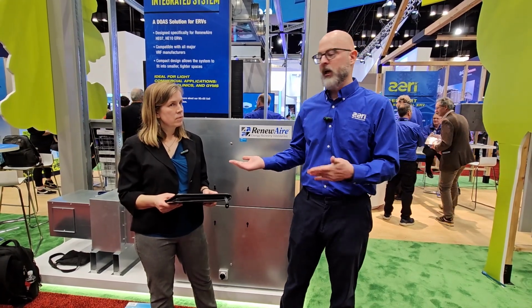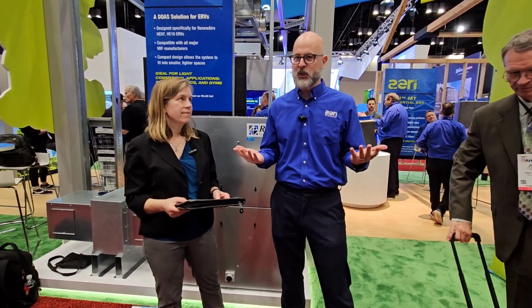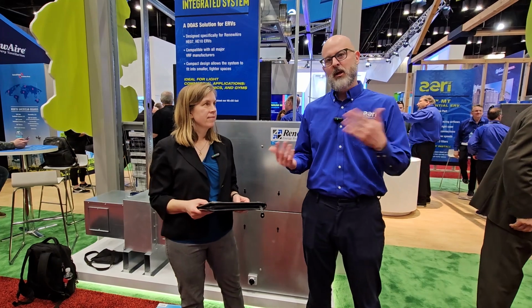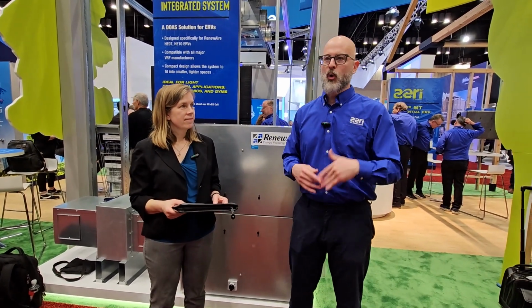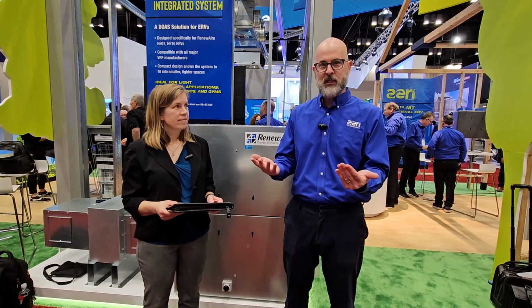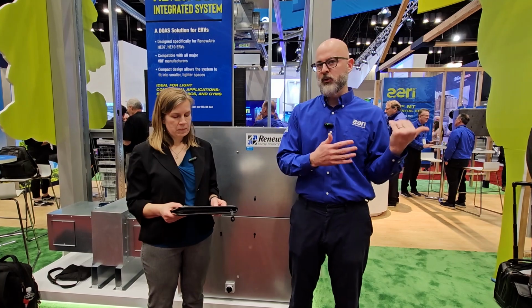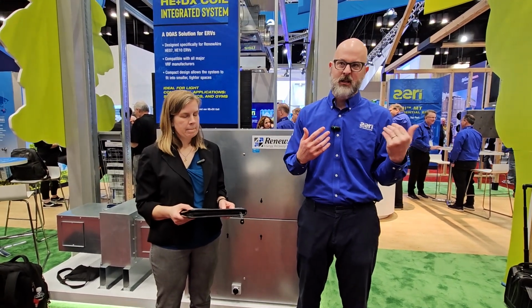So challenge-wise, let's say in Florida, we're in Orlando right now. It's very humid outside, and yet you have to still ventilate somehow. People need fresh air, whether we're in the Midwest or you're in the Southeast, right? We want to keep people healthy. So you're going to have to reject both the sensible and the latent energy regardless. And so that is why you use a plate heat exchanger to do that.